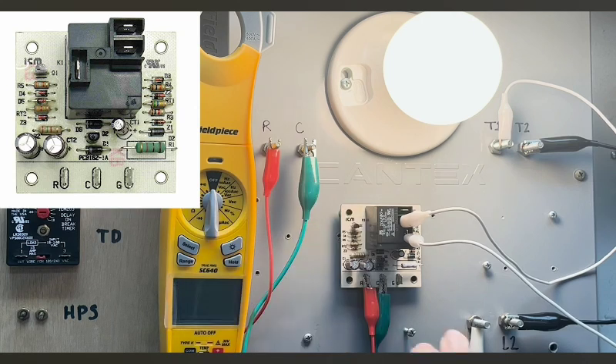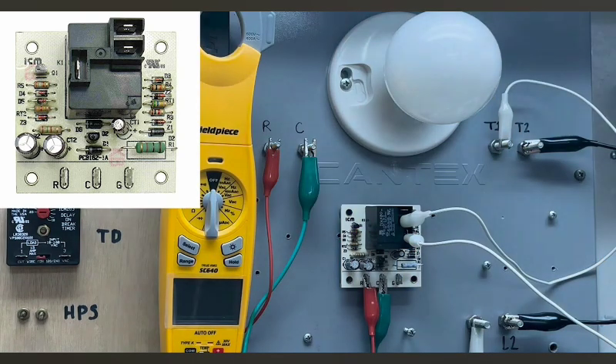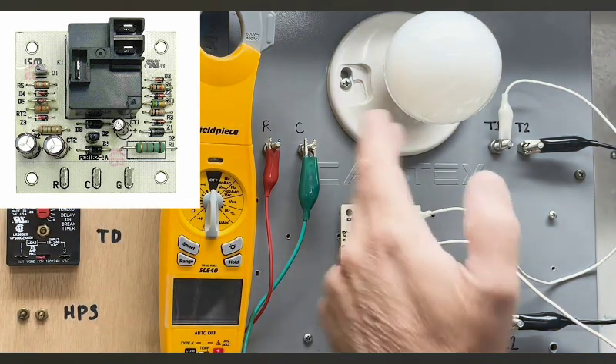This is a very easy board to wire up. Probably one of the most simple boards to wire up. There's no integrated fuses on this board. There's no additional wires that have to come on this board, such as W's, O's or Y's, Y2s, anything like that. So you couldn't use this board for a variable speed blower motor, but for a PSC motor or even just a standard ICM, you could use this board, because what you're doing is you're just trying to get the board to stay with the relay energized for about 50 seconds.